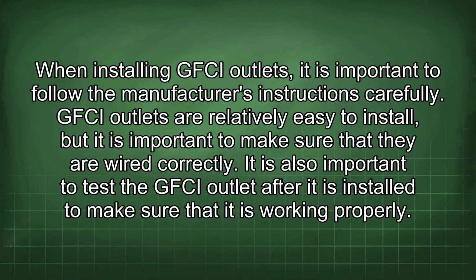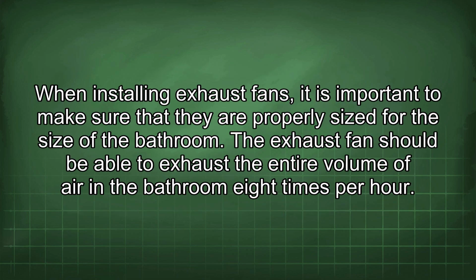When installing GFCI outlets, it is important to follow the manufacturer's instructions carefully. GFCI outlets are relatively easy to install, but it is important to make sure that they are wired correctly. It is also important to test the GFCI outlet after it is installed to make sure that it is working properly.